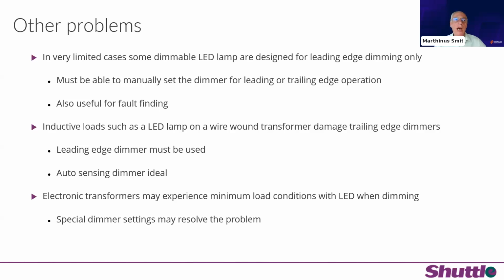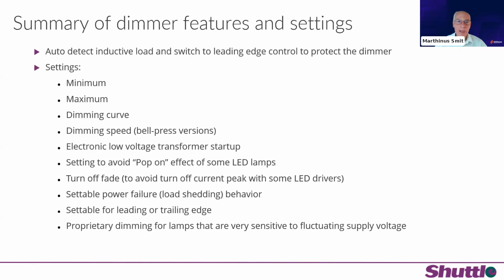We also find that some electronic transformers for low voltage LEDs, in the cases where they're still being used, like in zone 1s in wet environments and so on, sometimes the electronic transformer doesn't turn on, especially at low intensity or when the dimmer starts up, although the minimum load requirement of the electronic transformer is abided by. In that case, it's ideal to have a dimmer which has a special setting, which actually provides a turn-on kick pulse for the electronic transformer.